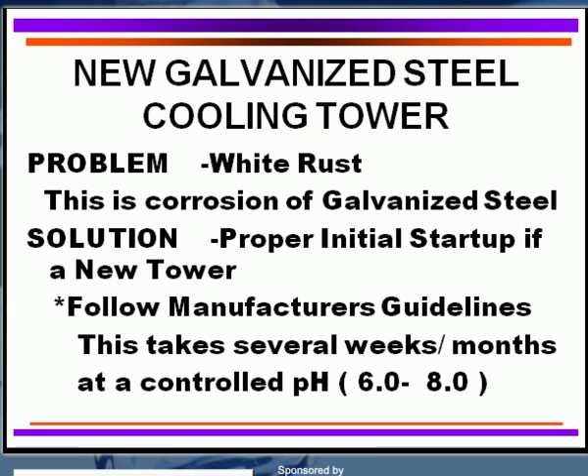The proper method to resolve this white rust problem on a new cooling tower is to start up that cooling tower properly from the water treatment standpoint. The guidelines from the manufacturer say you can do this in several weeks or several months by controlling the pH down in the range of six to eight, and you will gradually form a protective film on those galvanized steel surfaces. There are other techniques that can be utilized as well.